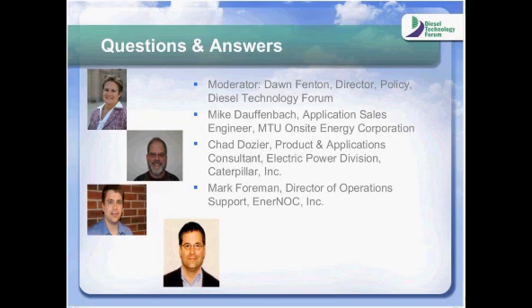You want to go first, Chad? Yeah—additives are still available to be used. You can still use additives, but you need to be aware that the additives you're using shouldn't raise the sulfur content of your fuel above 15 parts per million for ultra-low sulfur diesel. Also, a lot of manufacturers have a limit on the amount of additives you can use, like a 1-2% additive maximum.